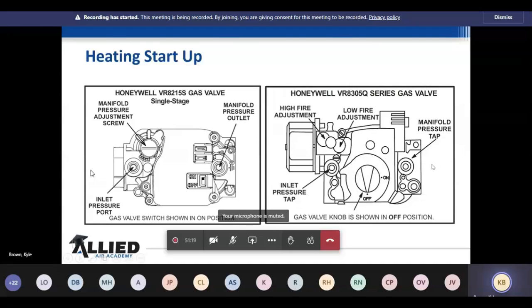But you'll see your inlet pressure tap and your manifold pressure, same thing here, because we have to check our pressures. On 2-stage units, you really need to make sure you check high fire and low fire, first stage and second stage, however you want to look at it. And if you have to make an adjustment on either one, I would suggest that you go back and check both of them 2 to 3 times. I have found that if you have to adjust the high fire, and you're at high altitude, especially in Denver at 5,000 feet, this is going to become really important to you. You want to double check that.